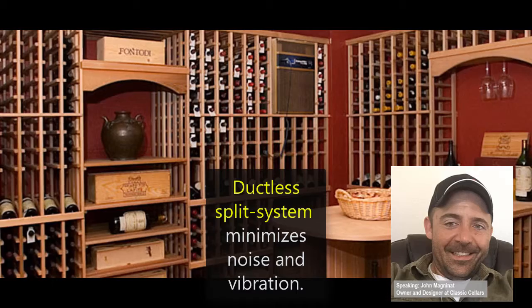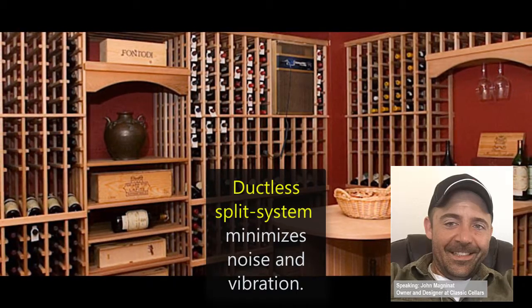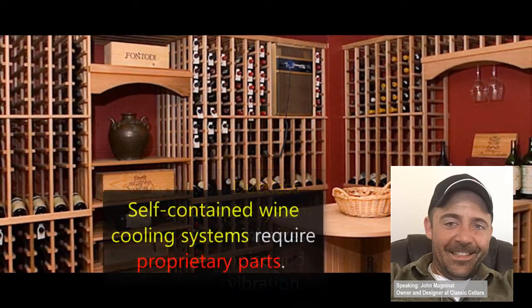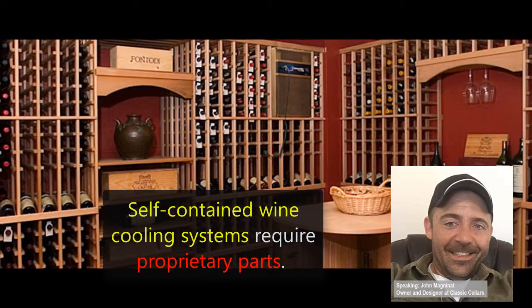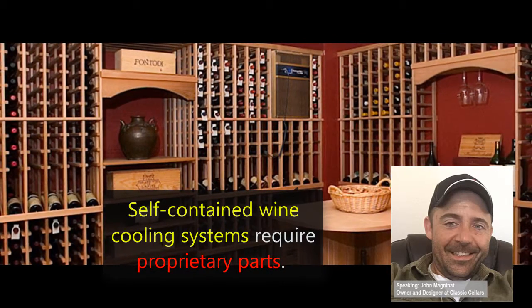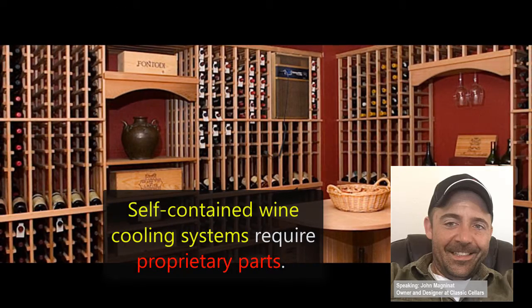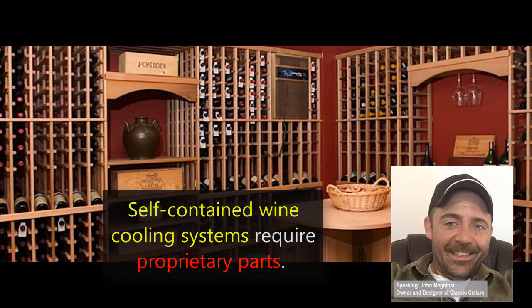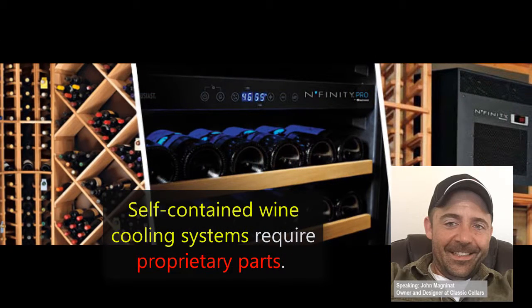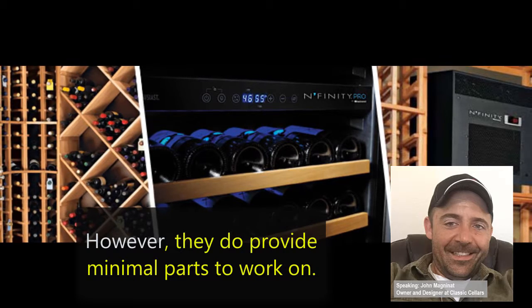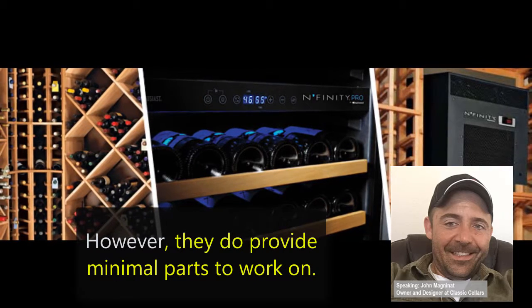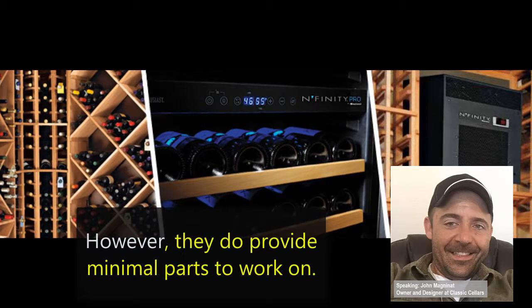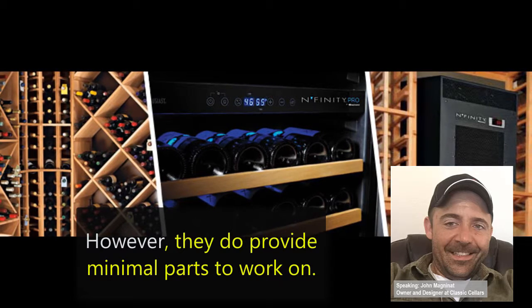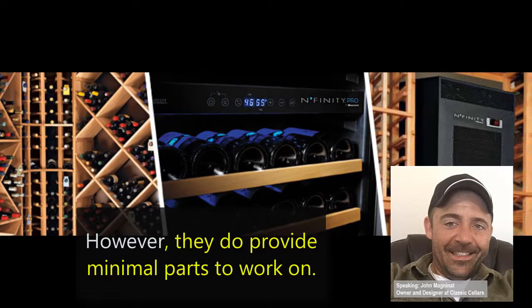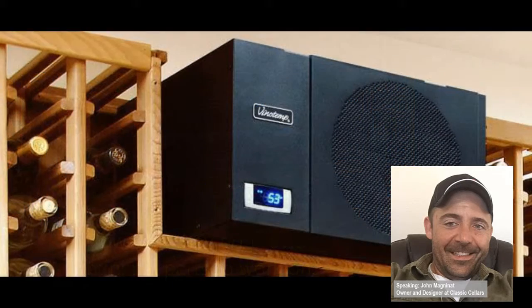With the self-contained units, you're going to find a lot more proprietary parts. So if something goes down, we're going to have to order it from the manufacturer and bring it in that way. But some of the remote condensing units for the split systems have to go far away from the unit, and with the self-contained ones, you don't have to worry about your refrigeration piping and power outside and stuff like that. We just need a power source inside there. They've both got pros and cons to them, so it really depends on where this thing is going.